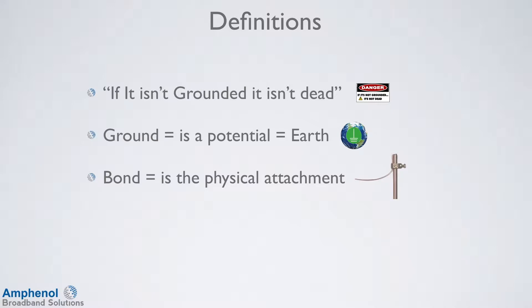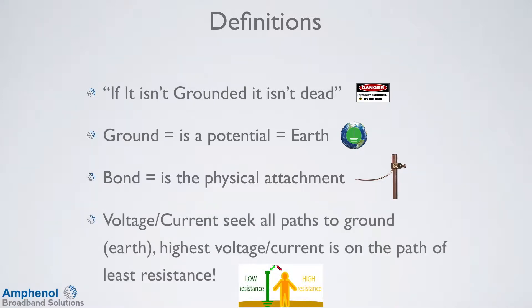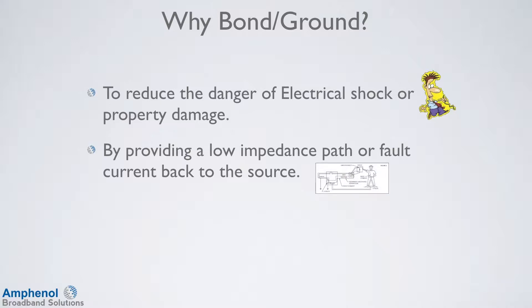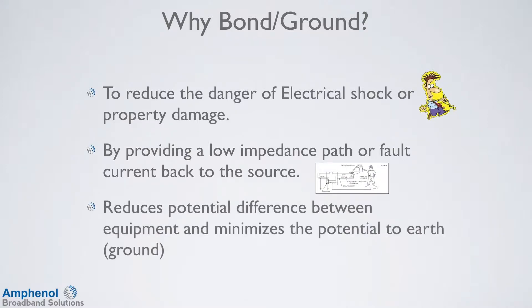In cable TV plant construction, we still put in grounds, but only on rare occasions when working on residential properties. These circumstances will be shown later. We've always been told that the path of least resistance carries the voltage and current — this is false. They seek all paths to ground, with the majority on the path of least resistance. We bond and ground to protect ourselves from electrical shock or damage to property and equipment. The bond and ground provides a low impedance path for fault current back to the source, reduces potential differences between equipment, and minimizes the potential to earth ground.